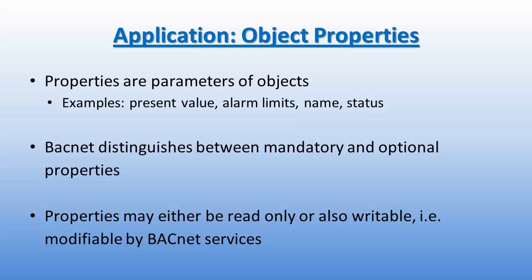BACnet also requires that certain objects support additional properties. The type of object and type of device in which that object resides determines which properties are present. BACnet objects have two classes of properties: mandatory and optional. BACnet distinguishes between the two, and like most other protocols, limits access to some of these properties. Properties may either be read-only or writable, and they are modifiable by BACnet services.